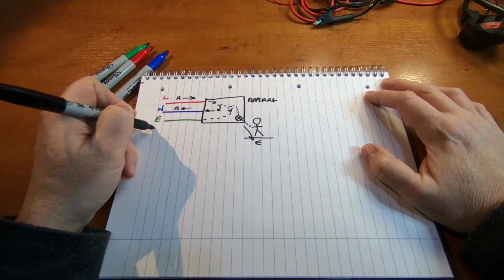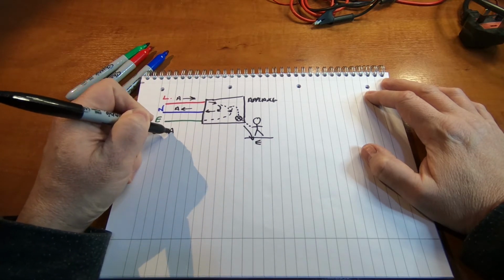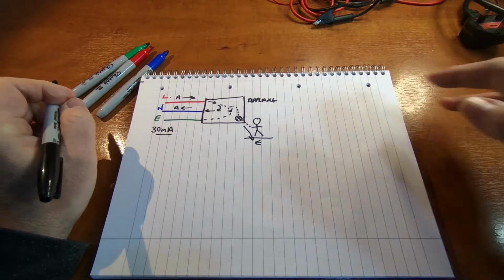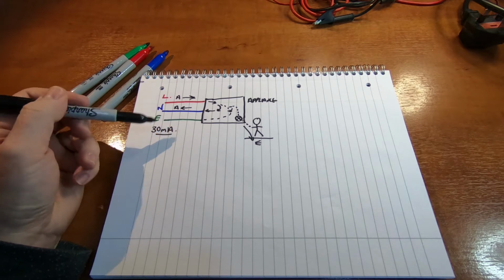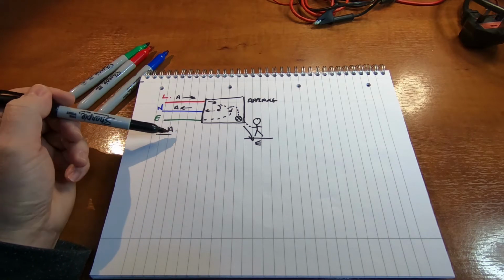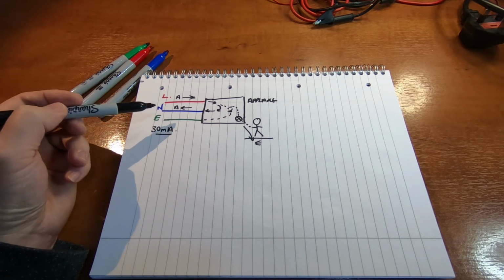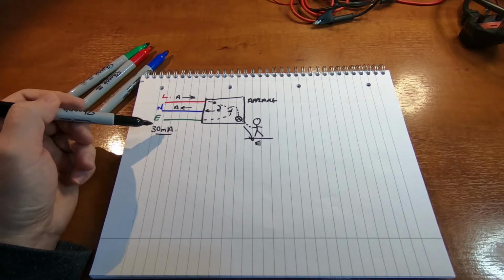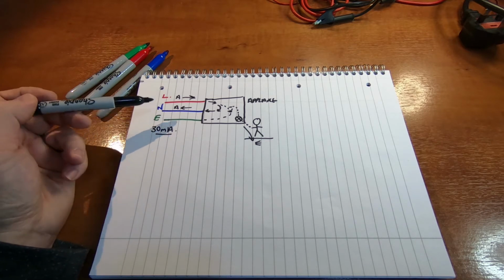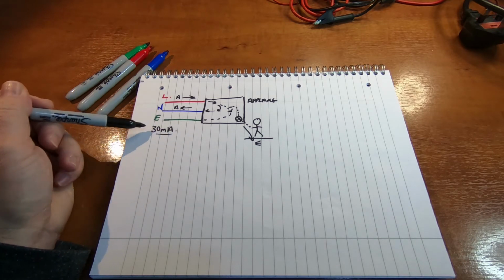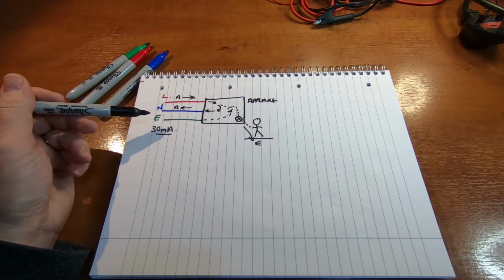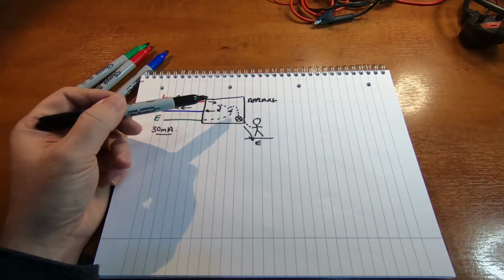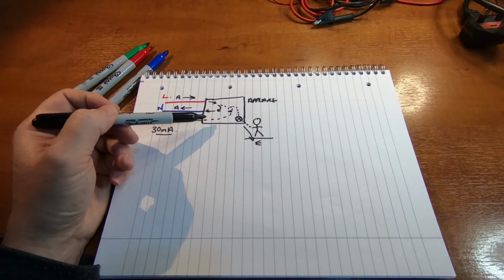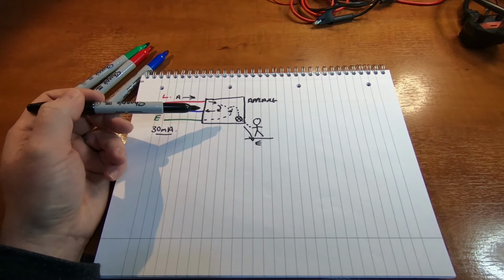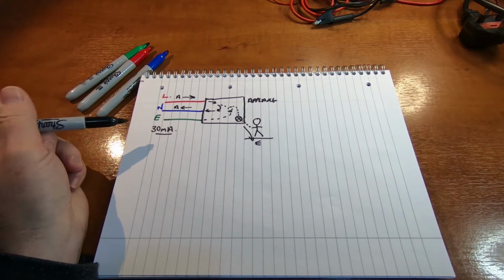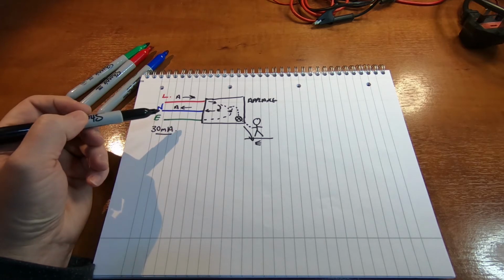And typically it's 30 milliamps is the detection before the fuse will trip. Now, the problem is in most homes, though it's changing now, where you have individual detectors on each different circuit, in most homes, mine included, there's only one of these RCD detectors for the whole of the house. So if this faulty appliance is plugged in somewhere, and it doesn't necessarily need to be turned on either, just plugged in, the RCD could be tripping every now and then, and nobody knows where that appliance is.